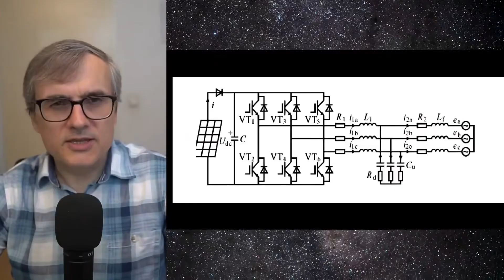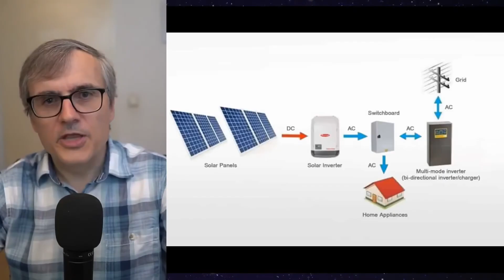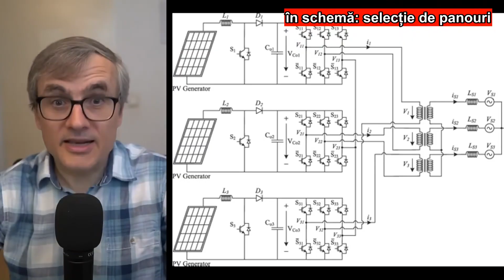Prosumers who have installed a three-phase system have an advantage. They distribute the energy across all three phases of the grid. The energy delivered on a single phase will be lower. Because of this, three-phase systems disconnect from the grid less often, which benefits the prosumers who have them. In addition, when the three-phase inverter is more complex, for example, being built from three separate single-phase inverters, it is possible to deliver energy on those phases of the grid that have a lower voltage.